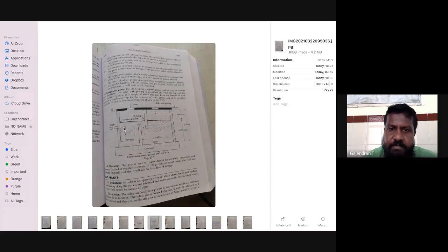And this is another intervention of how a grease and oil trap could be done, wherein these are baffle walls where you can see a wall from the bottom as well as a wall from the top. So what happens here is once it comes in here, the contents tend to be floating on the top, and you can see the outlet has got a downward looking pipe. So only the liquid at the bottom goes into the outlets, whereas the grease and oil which are trapped on the top are removed through the cover.